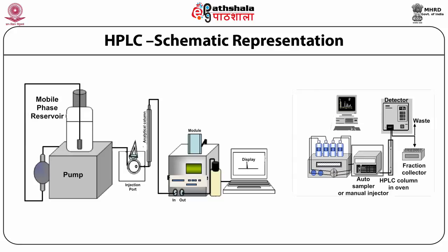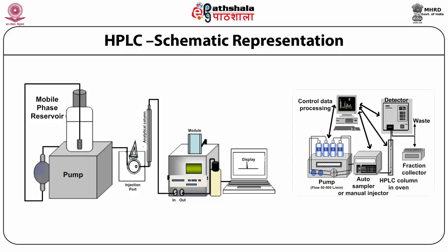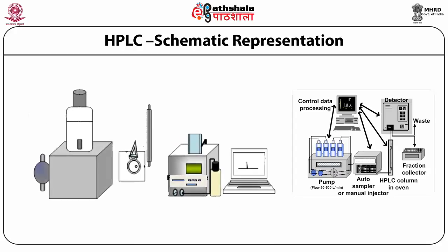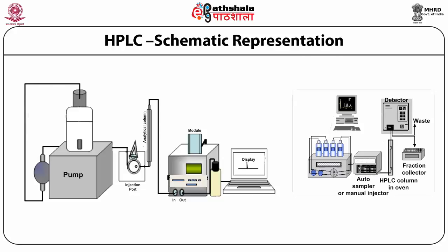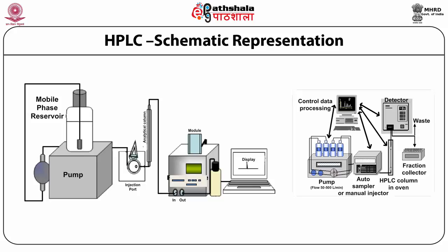The pump never produces pressure; it works only for flow rate, but pressure is exerted by the column depending on the particle size of the stationary phase. If the particle size decreases, surface area increases and back pressure increases. Between the column and the pump, an injection port — almost 99% of HPLCs today use a Rheodyne injector — allows sample injection without disturbing the flow. Once the sample is loaded, it is applied onto the analytical column where mobile phase continuously elutes it.